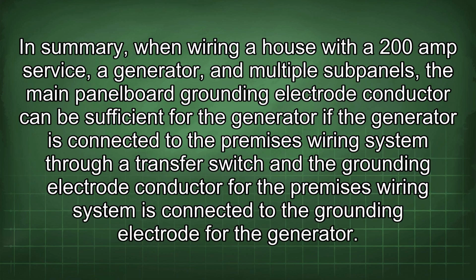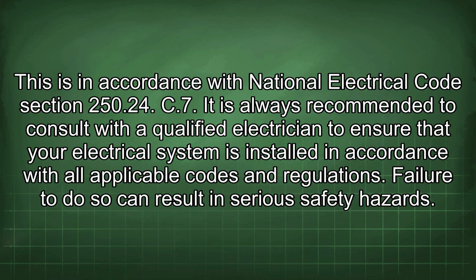In summary, when wiring a house with a 200 amp service, a generator, and multiple subpanels, the main panel board grounding electrode conductor can be sufficient for the generator if the generator is connected to the premises wiring system through a transfer switch and the grounding electrode conductor for the premises wiring system is connected to the grounding electrode for the generator. This is in accordance with National Electrical Code Section 250.24(C)(7). It is always recommended to consult with a qualified electrician to ensure that your electrical system is installed in accordance with all applicable codes and regulations. Failure to do so can result in serious safety hazards.